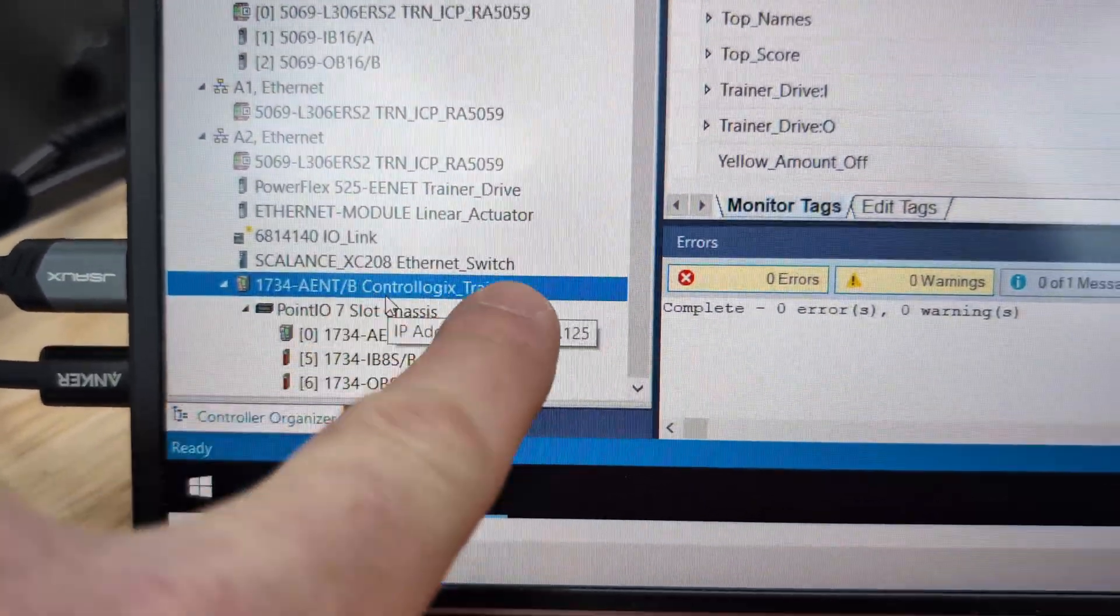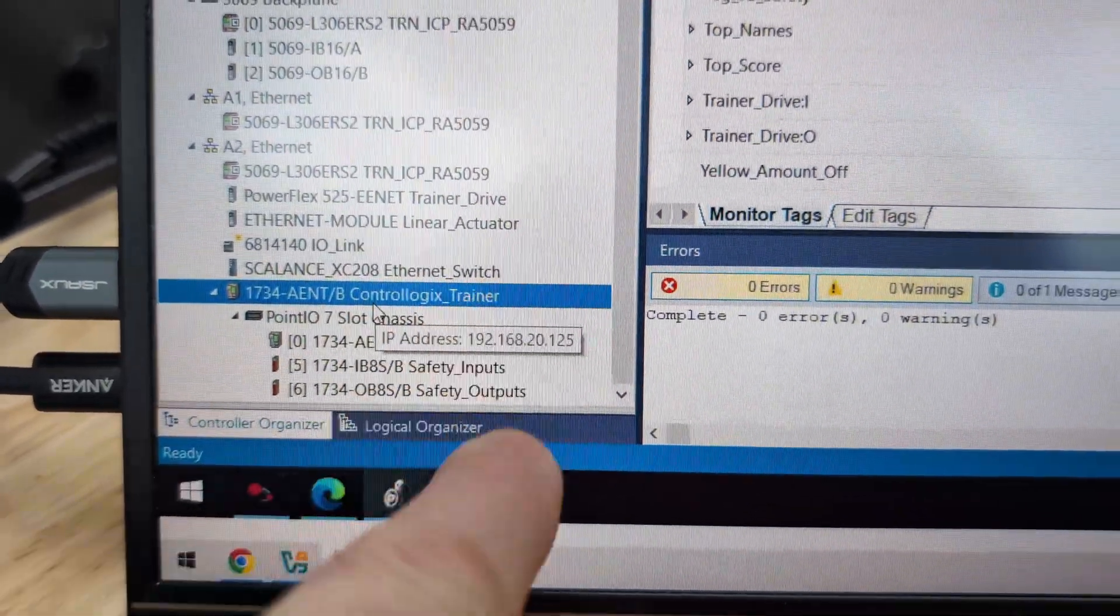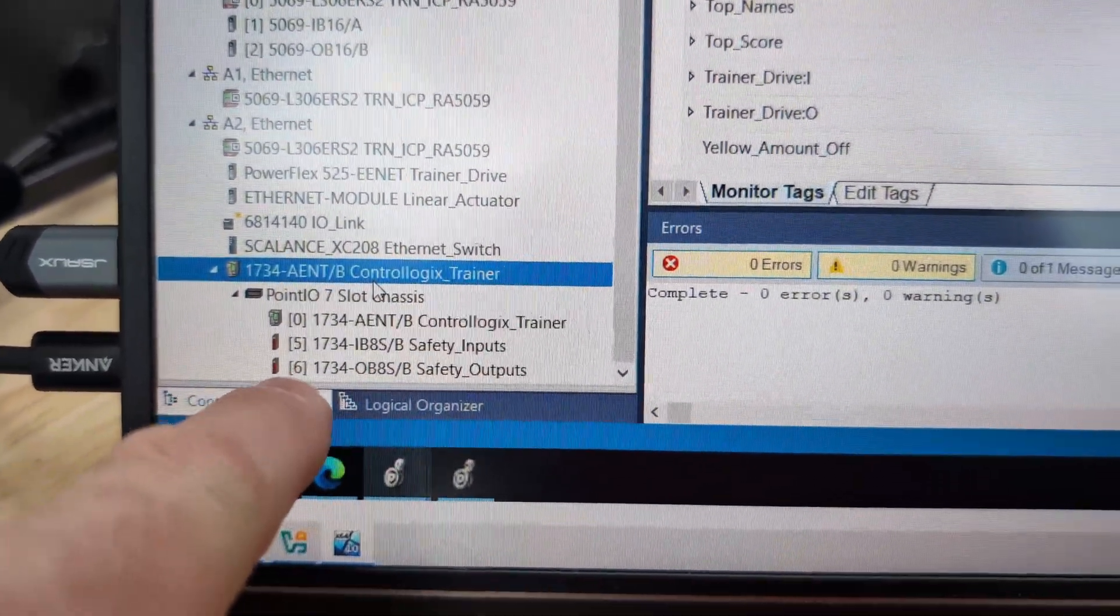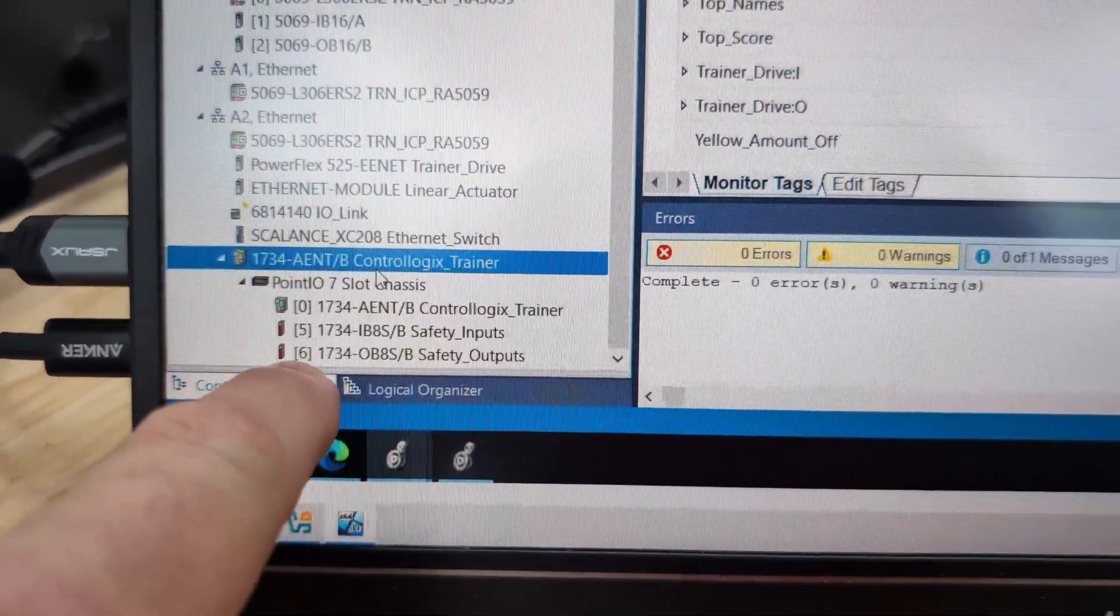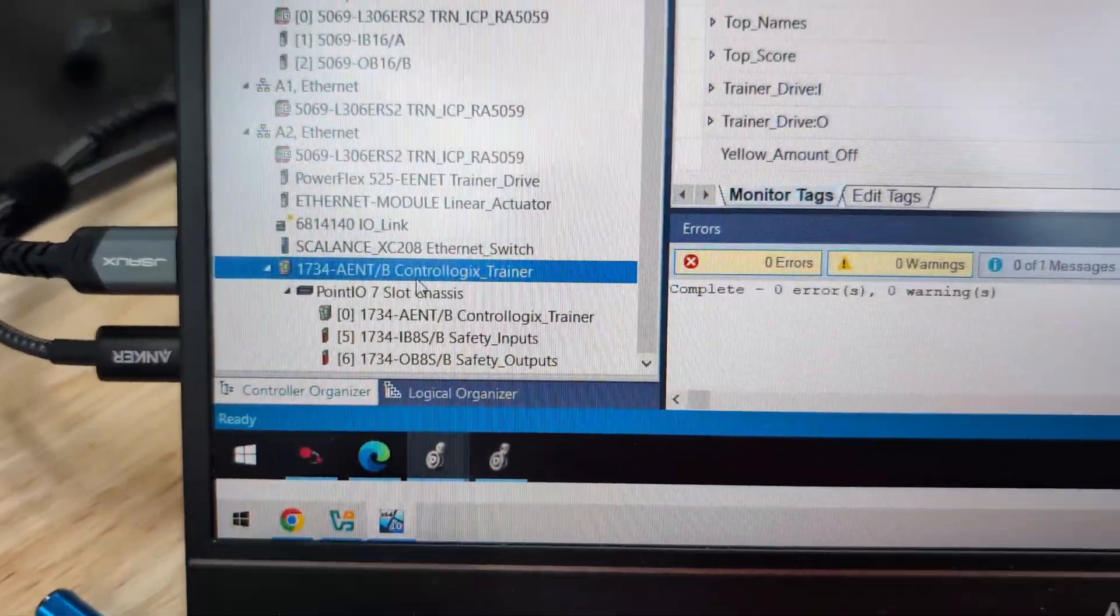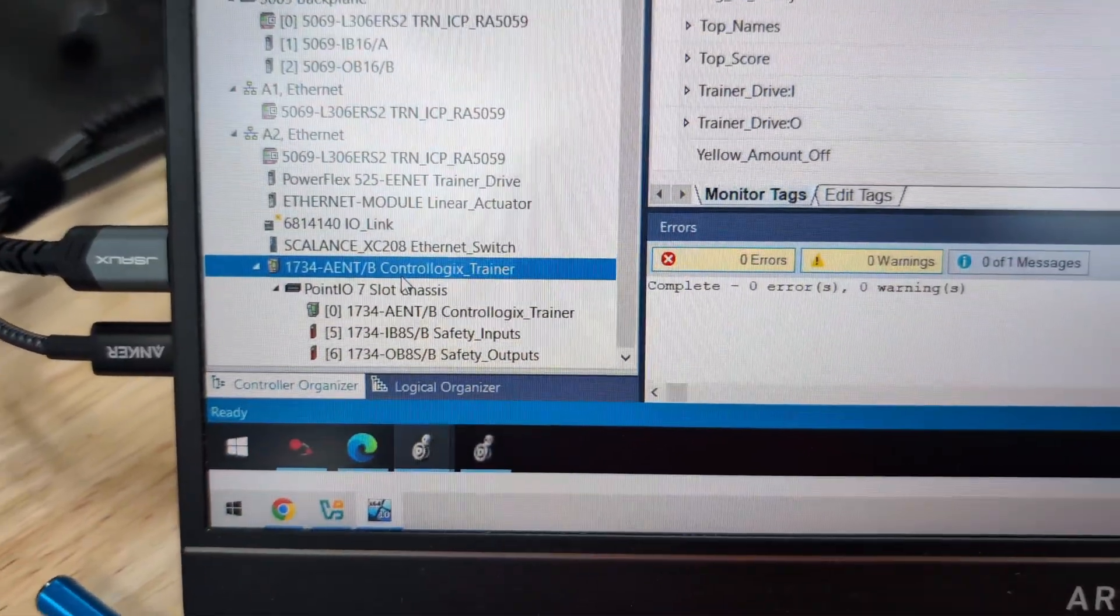So all I can really do with that info I have now is go over into my I/O configuration. And if we go down, then we mouse over them all. There's 192.168.20.125. And I know it's this output module. So I'm going to use this piece to figure out its name. That's going to be the ControlLogix_Trainer:6. And then since it's output, :O.